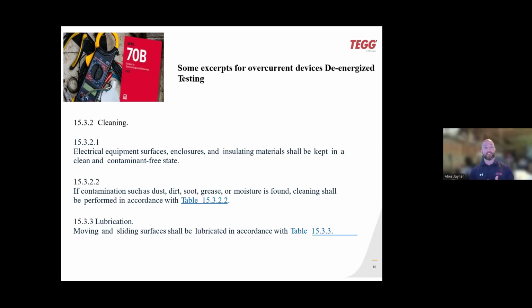We were trying to figure out whether it was a possum, a raccoon, a squirrel, or a chipmunk, because all there was just a skull. That skull was just left over. So it's very important to make sure that the cleaning inside there and the proper care for the gear is taken seriously. Clogging up for insulation inside this gear is not just for the rodents, but for the future if people are trying to run new conduits or new wires in there and they don't want to send a snake down or something.